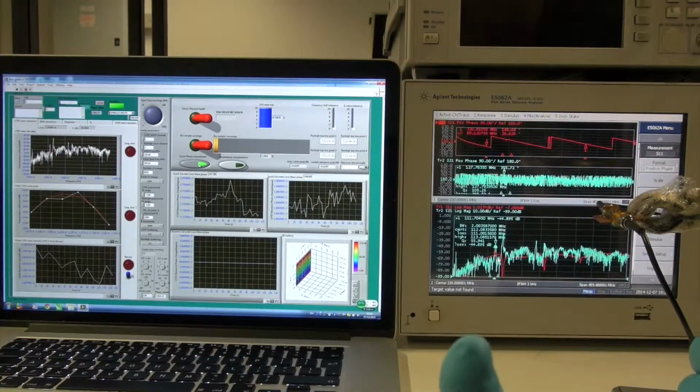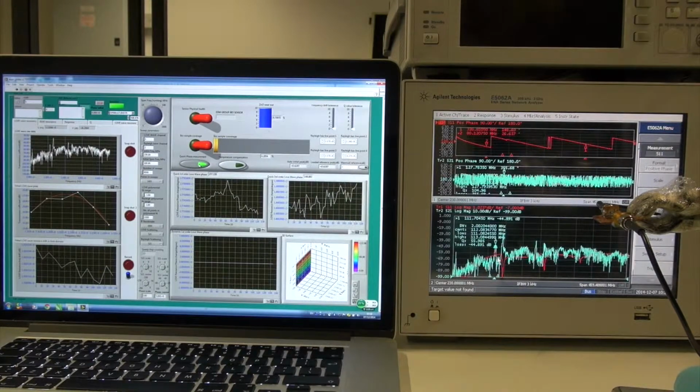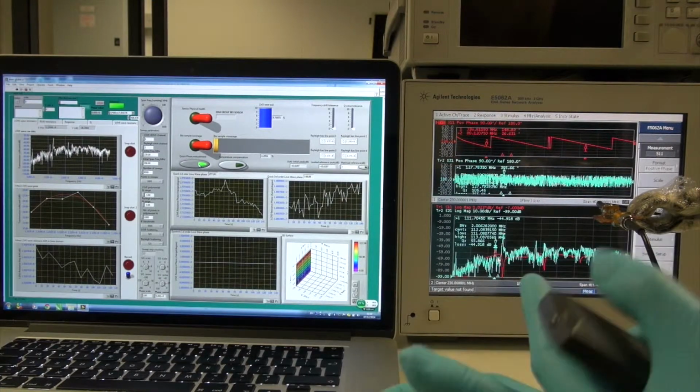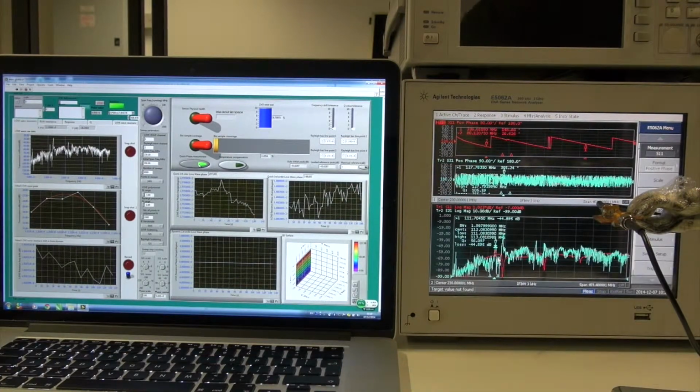But the high piezoelectric coefficient substrate is also very sensitive to the temperature. So this makes it difficult to distinguish the phase change between mass load and temperature drift. So we need to remove this temperature drift effect from the final measurement result.